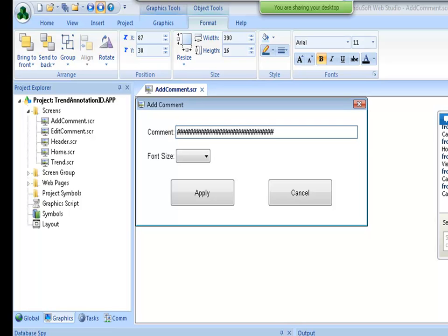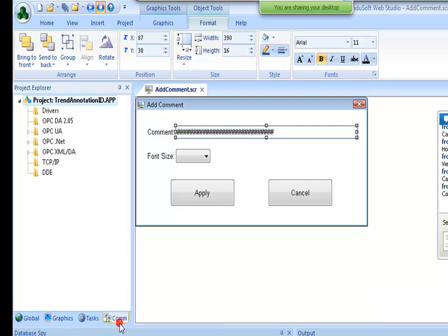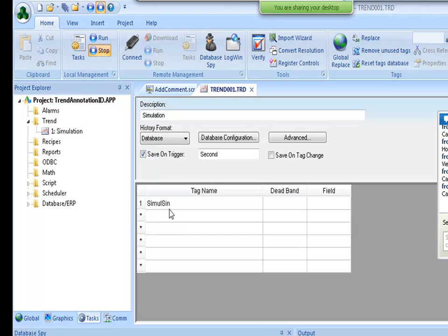The rule of thumb, I would say, if you are saving data into the HST proprietary files, create up to 100 or tops 140 tags or so in each worksheet, because each worksheet will create a different file. So by this way you make sure the files don't get huge, like gigabytes or terabytes for each file. So the time to query data from those files is much smaller.